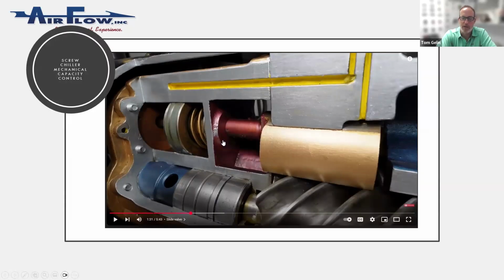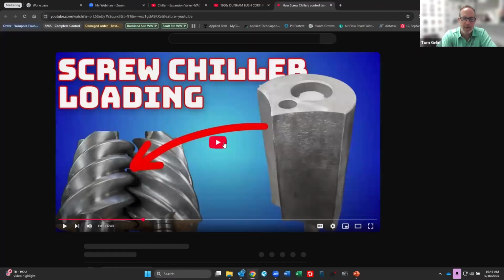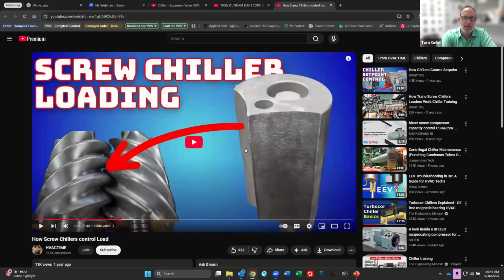If you've ever tried to turn down a centrifugal fan beyond 30%—we don't do this often because we usually don't turn fans down that far—but if you block off part of the wheel with a mechanical device, you can get the turndown of a fan much lower than, say, 40 or 30%. There's a similar concept, though much slower moving, with a device that helps with low capacity control on a screw chiller, which this video sort of shows.